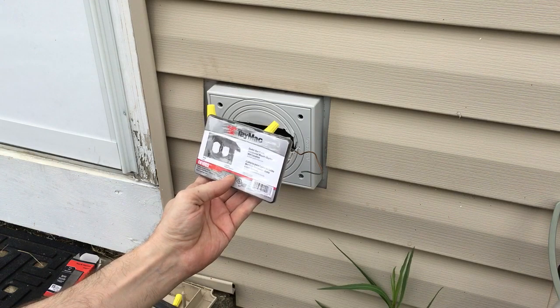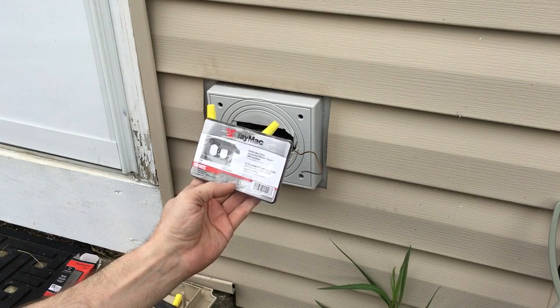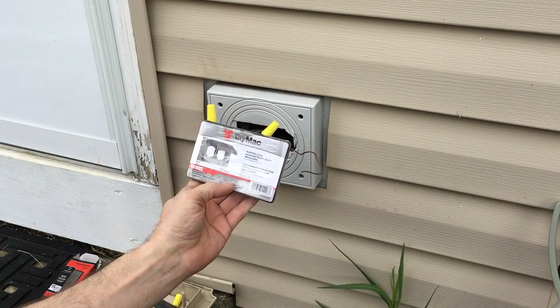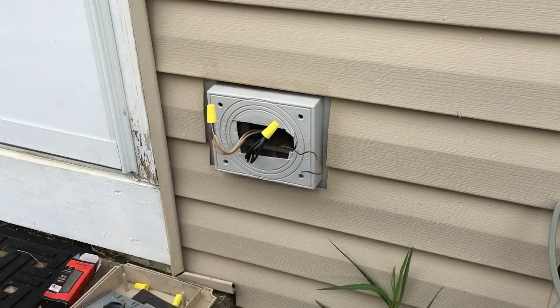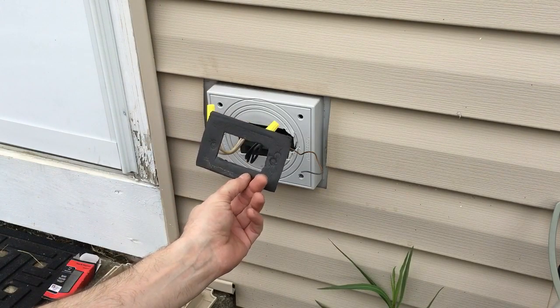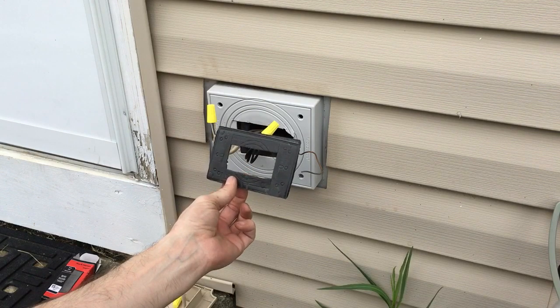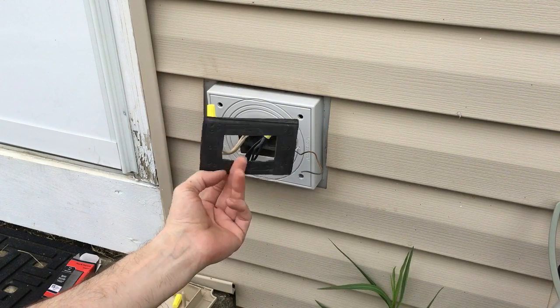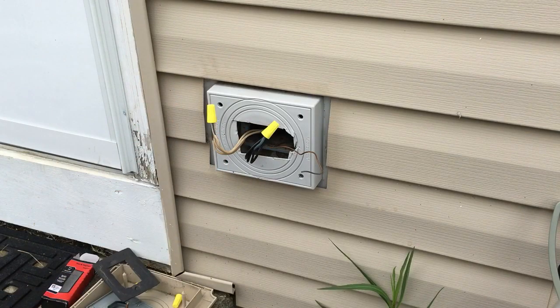Whether or not I actually found any type of moisture inside of it, it's a horizontal mount, duplex wet location outlet box cover. The seals on this are probably getting worn out from the same kind of weathering, the hard winters and hot summers. For another $5, and being 21 years old, might as well go ahead and replace that as well.